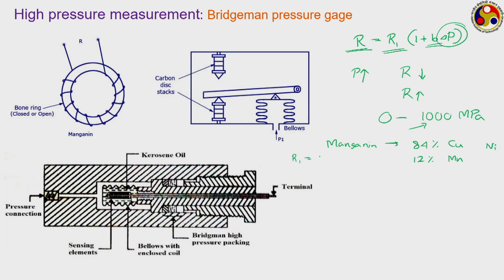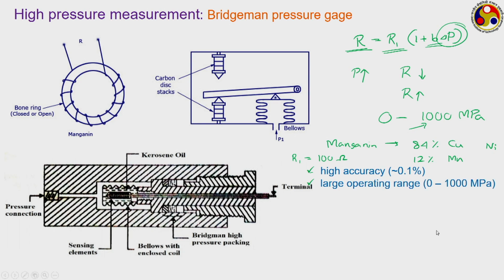Generally we choose a resistor of 100 ohm under common atmospheric condition, and it has a B value of 2.5 into 10 to the power minus 11 Pascal inverse. So, the B value is quite small, accordingly we can keep on using it for quite a high pressure range. The biggest advantage of this one is high accuracy, of the order of 10 to the power minus 10 to 0.1%. Then large operating range, as I have mentioned, particularly suitable for high pressures, and excellent dynamic response, so we can use them for both static and dynamic pressure measurement.